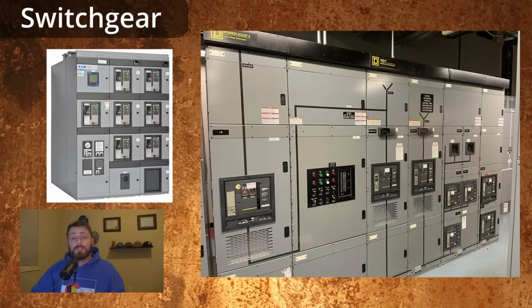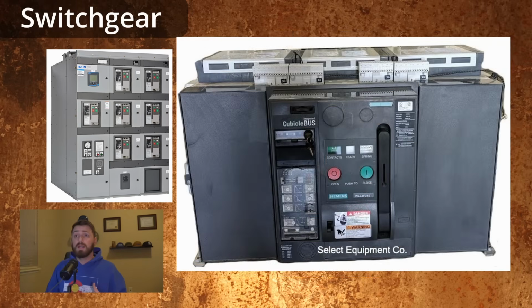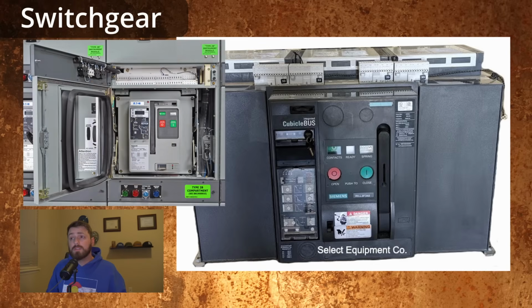Switchgear can look similar to a switchboard at first, but it's notable for having isolated cubicles for each feeder breaker or switch. These are found in heavy industry and utilities where a ton of power is getting distributed. Voltages range from 480 volts all the way up to 15 or even 35,000 volts. Typical 480 volt switchgear will have a main breaker rated for 1,200 to 4,000 amps, with feeder breakers sized for 300 to 1,200 amps, give or take.